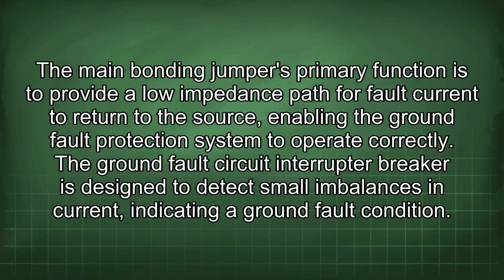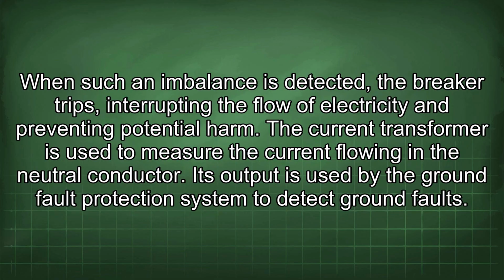The main bonding jumper's primary function is to provide a low impedance path for fault current to return to the source, enabling the ground fault protection system to operate correctly. The ground fault circuit interrupter breaker is designed to detect small imbalances in current, indicating a ground fault condition. When such an imbalance is detected, the breaker trips, interrupting the flow of electricity and preventing potential harm. The current transformer is used to measure the current flowing in the neutral conductor. Its output is used by the ground fault protection system to detect ground faults.